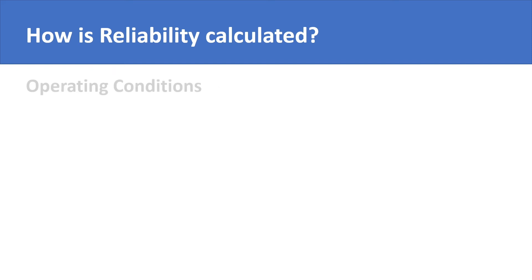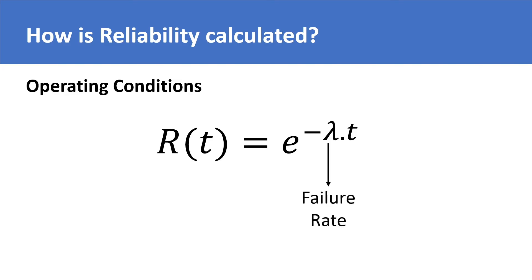An important thing to remember when using the formula of reliability is about the operating conditions. When calculating the failure rate, always remember to use historical data of machines with same or similar operating conditions. In the example of our pump, don't plug in the failure rate of a pump that maybe handles a different fluid, because then the operating conditions are not same.